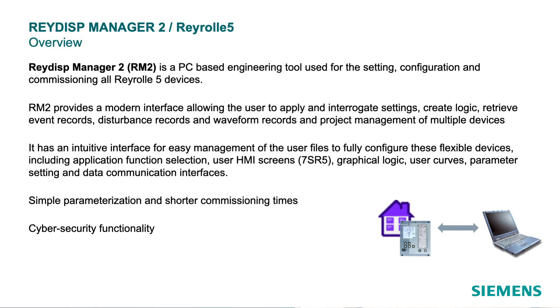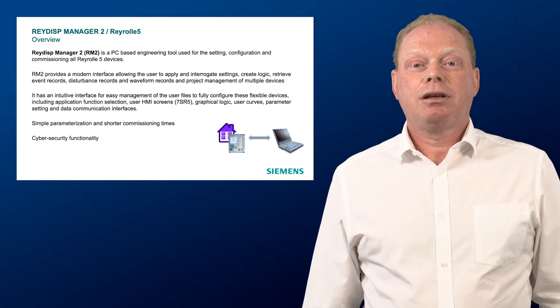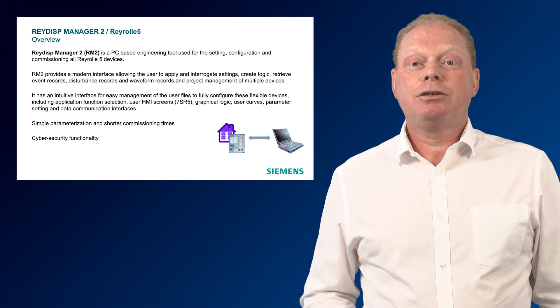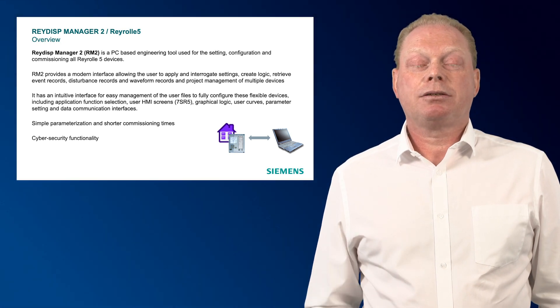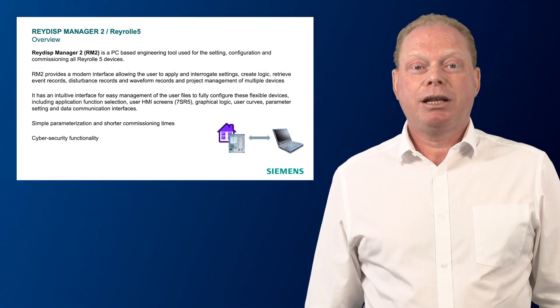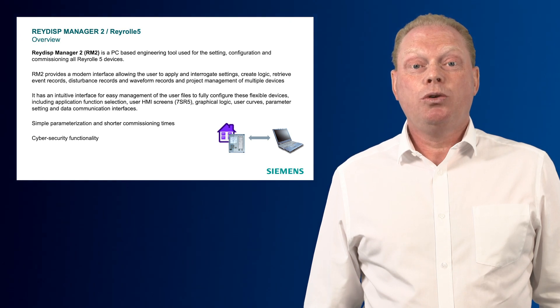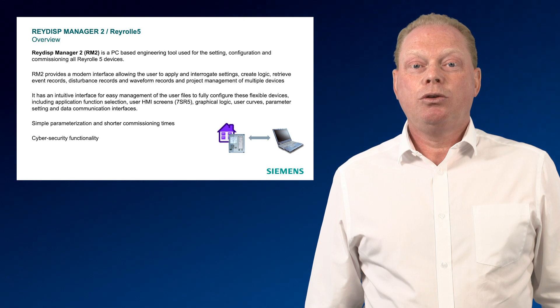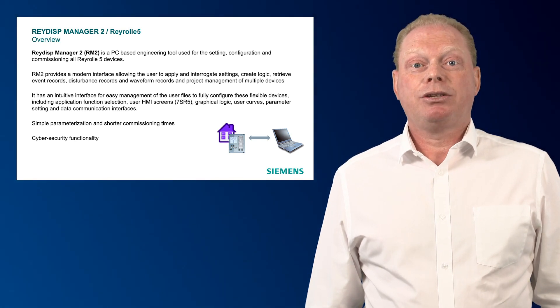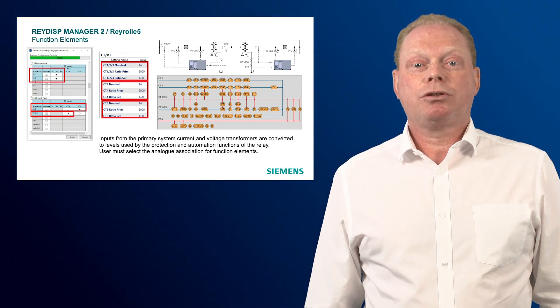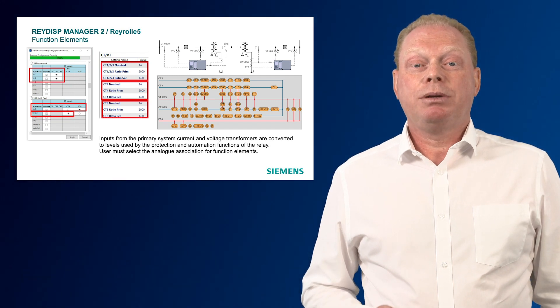Reydisp Manager 2 (RM2) is a PC-based engineering tool used for setting, configuration and commissioning of all Reyrolle 5 devices. RM2 provides a modern interface allowing the user to apply and interrogate settings, create logic, retrieve event records, disturbance records and waveform records, and project management of multiple devices. It has an intuitive interface for easy management of user files to fully configure these flexible devices including application function selection, user HMI screens, graphical logic, user curves, parameter setting and data communication interfaces. The Reyrolle 5 can be configured to meet all applications including which current transformer inputs are used by the functions. This flexibility allows the same product to be used for multiple solutions.